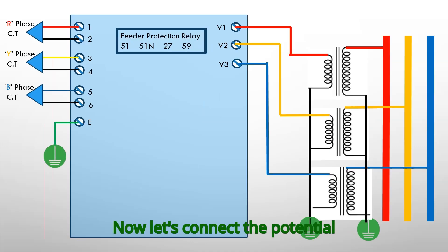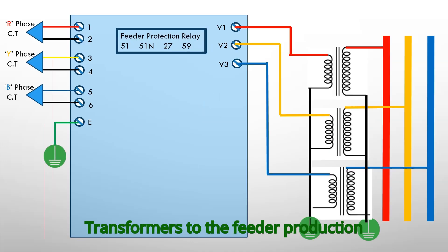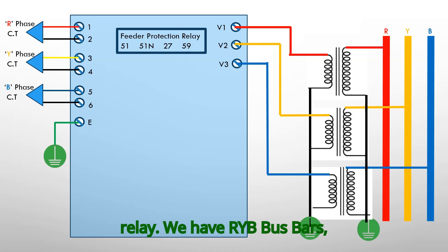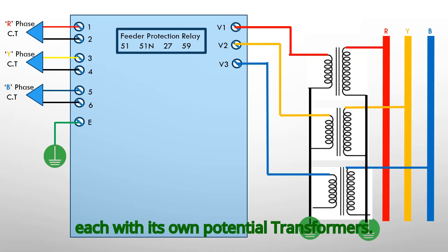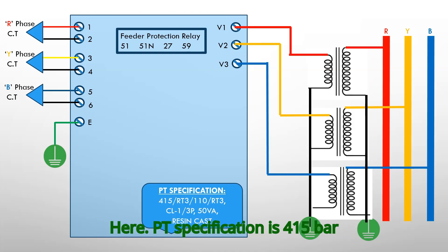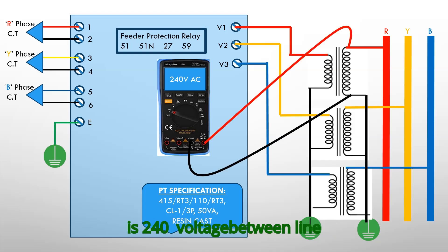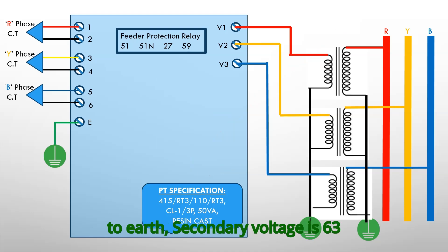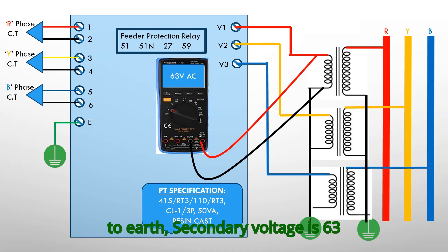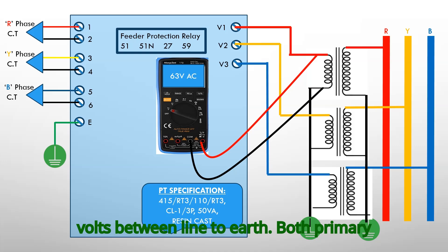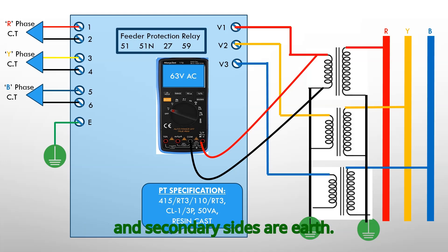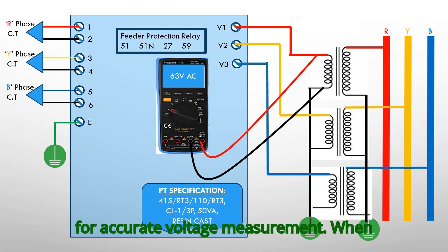Now let's connect the potential transformers to the feeder protection relay. We have R, Y, B bus bars, each with its own potential transformer. The PT specification is 415/√3 primary and 110/√3 secondary, indicating a primary voltage of 240V AC line-to-earth and a secondary voltage of 63V line-to-earth. Both primary and secondary sides are earthed. Understanding PT connection is crucial for accurate voltage measurement.